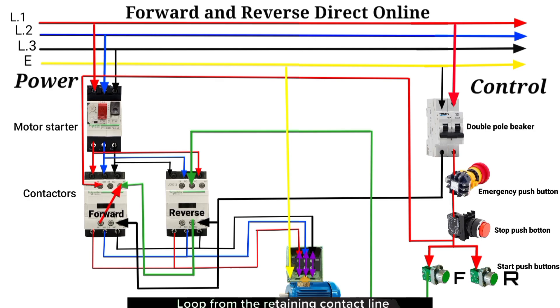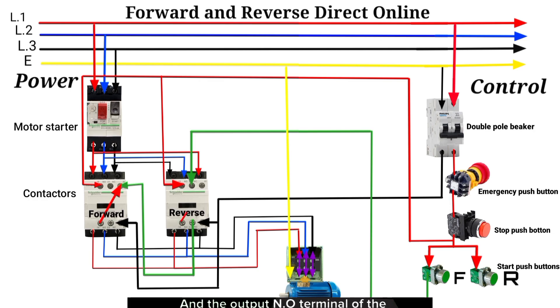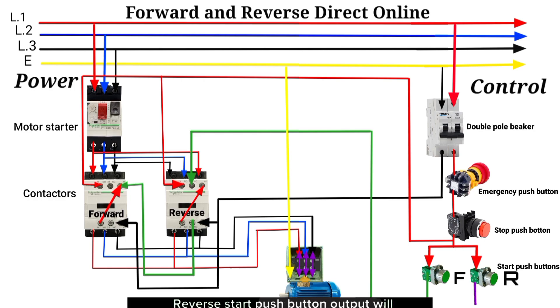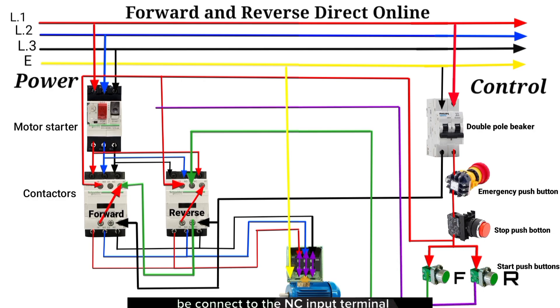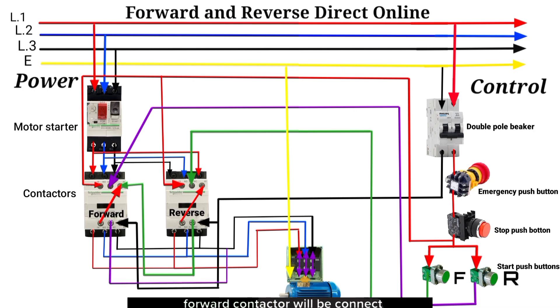Loop from the retaining contact line source and connect it to the NO input terminal of the reverse contactor, and the NO output terminal of the reverse contactor to A1 of the reverse contactor. The reverse start push button output connects to the NC input terminal of the forward contactor, and the NC output terminal of the forward contactor connects to the A1 terminal of the reverse contactor.